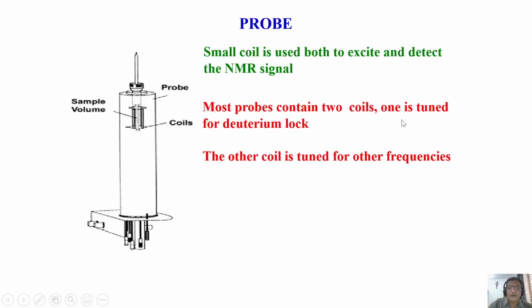Most probes contain two coils. Okay, you may ask me why two coils? Of course, one single coil does the job of both excitation and detection. Only a single coil, that will do for NMR. It will send the RF pulse, and detect the signal also. But there is another coil, which is also kept, that is for tuning to the deuterium frequency of the spectrometer.